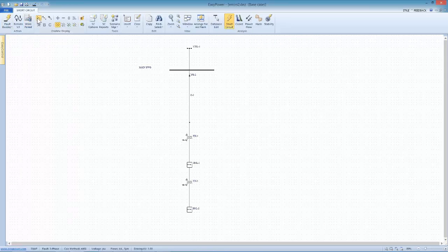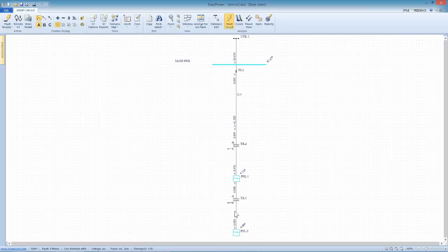What I'm looking for here is a half-cycle, three-phase fault. As I fault the buses, you can see I get some nice colors and numbers which tell me short-circuit currents, which at first blush all seems adequate. Then when I go to calculate arc flash incident energy, nothing happens. Okay, well, Jim said I'd see something here. Next thing is to call tech support.